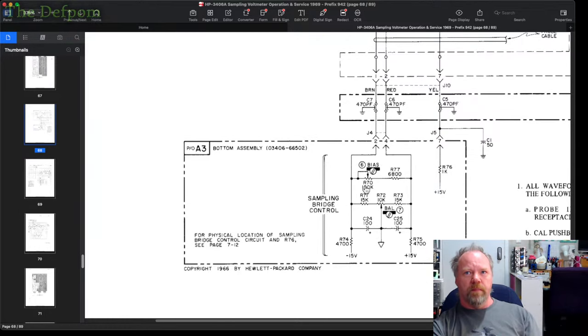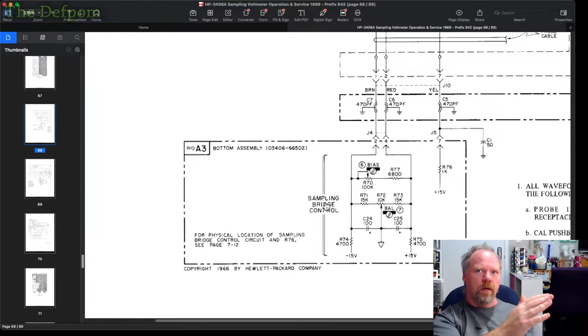We've got this biasing and balance adjustment here. Now, I've actually tried adjusting these. If I adjust the balance all the way one way, I can pull the needle down. I can actually get that 0.0 volt or 0.03 volt range to show a reading. I pull this all the way to one side, so it's biasing and unbalancing the bridge to one direction quite a bit. So that's probably a clue as well.